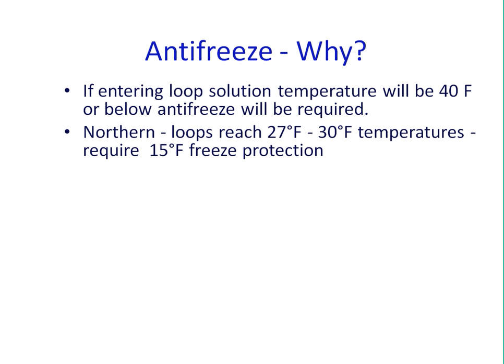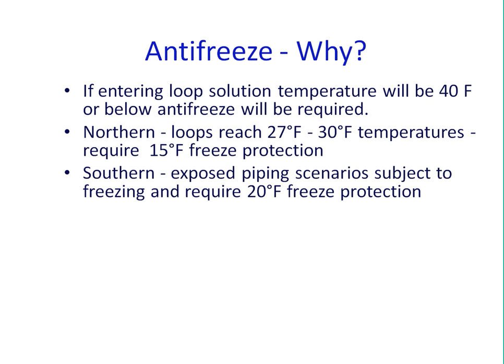You're tap dancing with a freezing condition. In the northern or heating dominant climates, your loop temperatures can reach from the mid-20s to around 30 degrees. If that's the case where you're going to be applying this particular loop design, then you want to make sure that you're applying enough antifreeze to get your freeze protection down to about 15 degrees. Even in the southern states, with southern exposed piping scenarios, in other words, if you are placing a unit on a rooftop, in an attic, or in an exterior enclosure, where that environment will start to see some freezing conditions, you may want to put some antifreeze in. You don't necessarily have to get down to 15 degrees, but you want to make sure that you're protecting your heat exchanger and internal components of the heat pump.